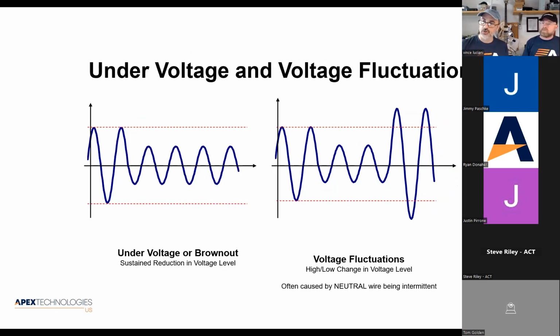The power could also go under its level. A couple of reasons for that. Sometimes you have voltage sags, which are very short-lived voltage fluctuations, usually in the downward direction. If the voltage is reduced and it stays that way for a long time, that's called a brownout situation. Where do brownouts come from? Overuse of the grid, right?